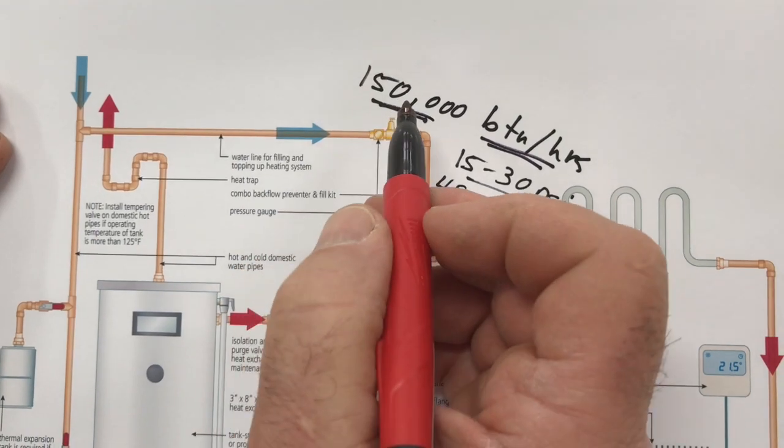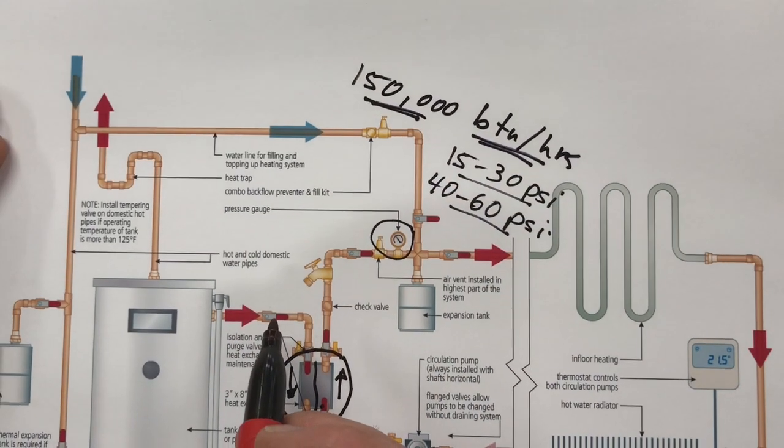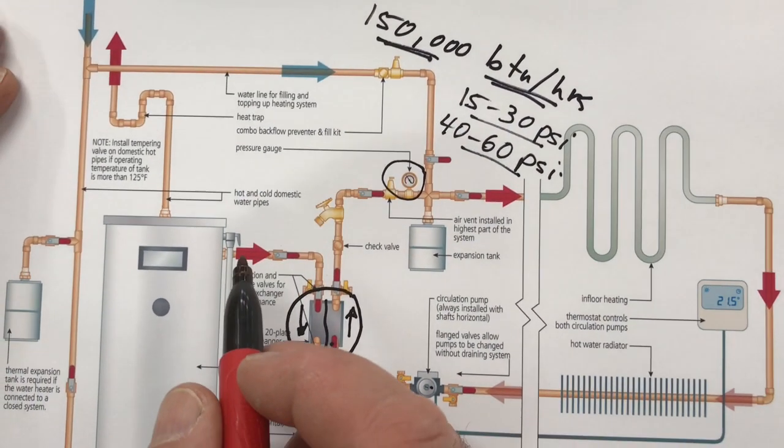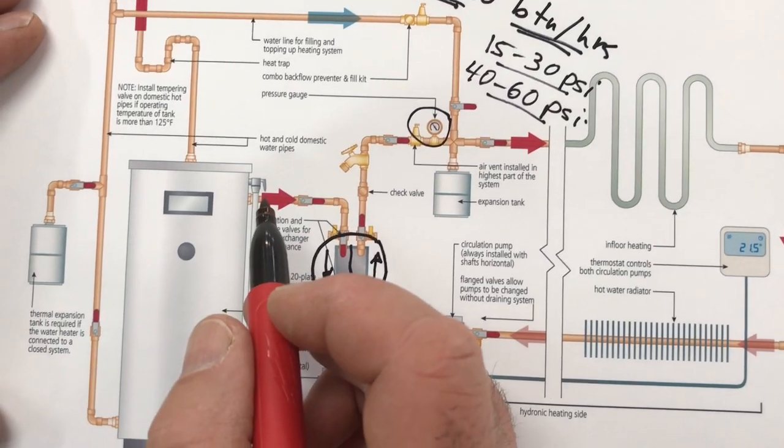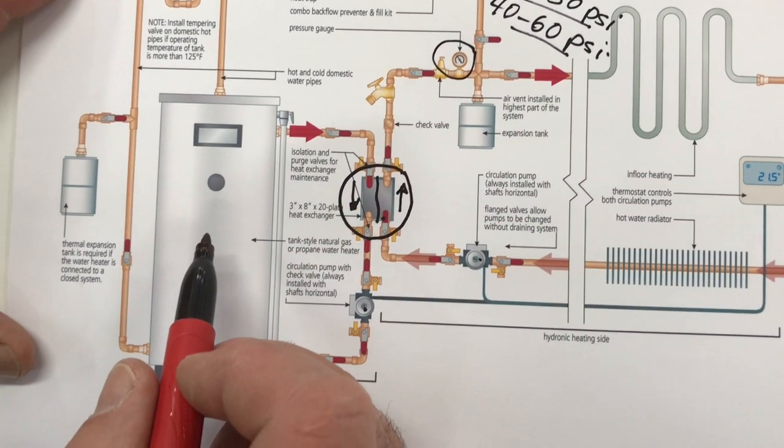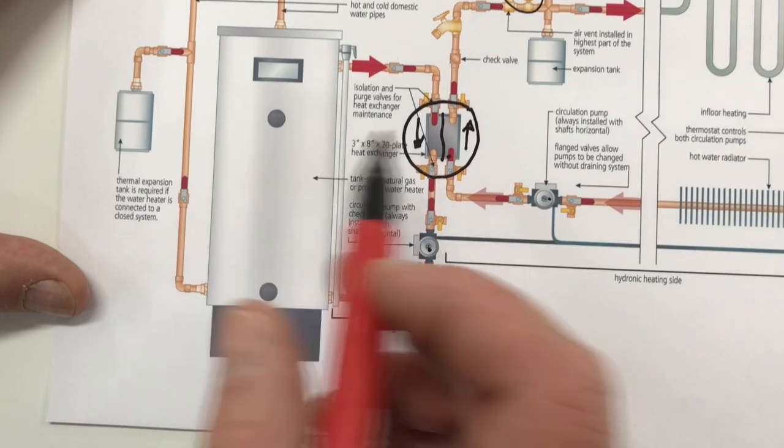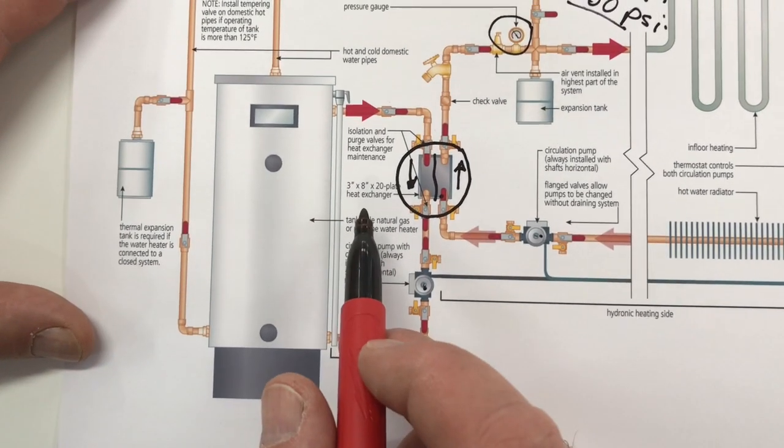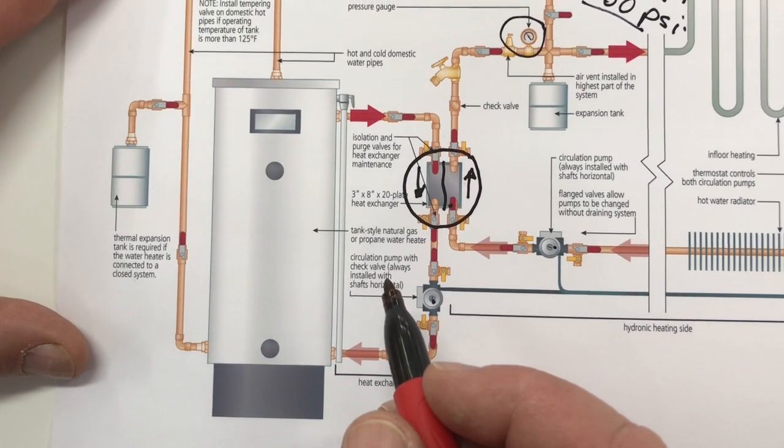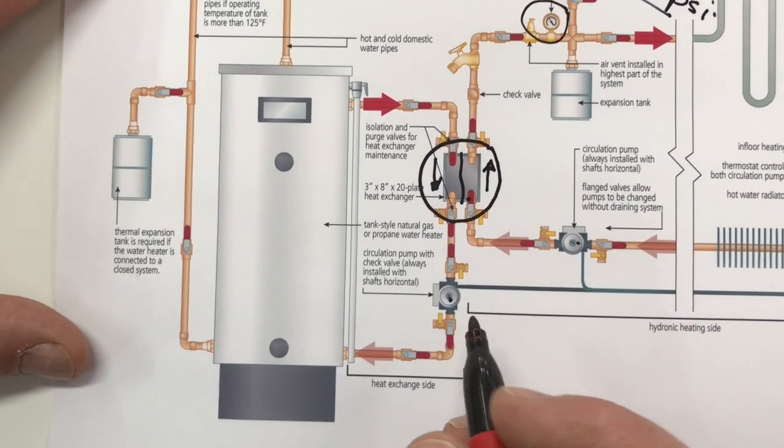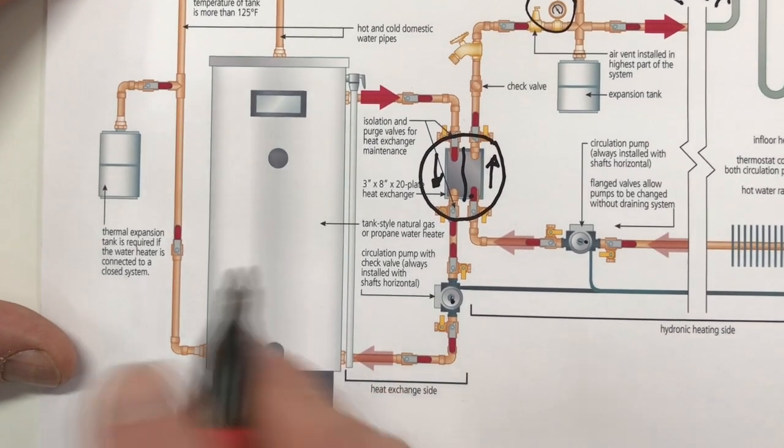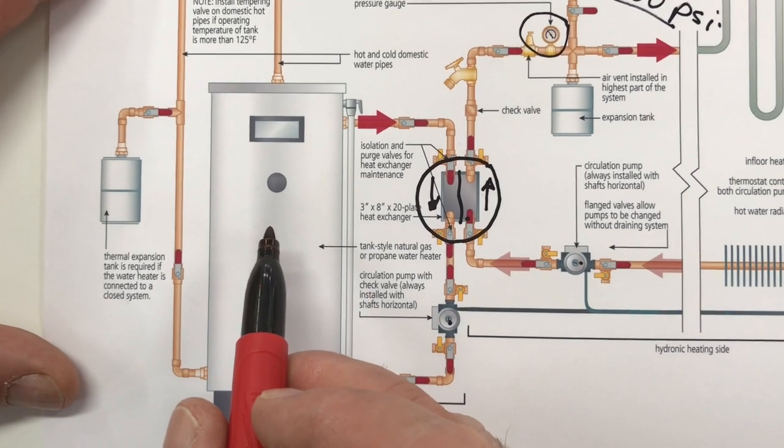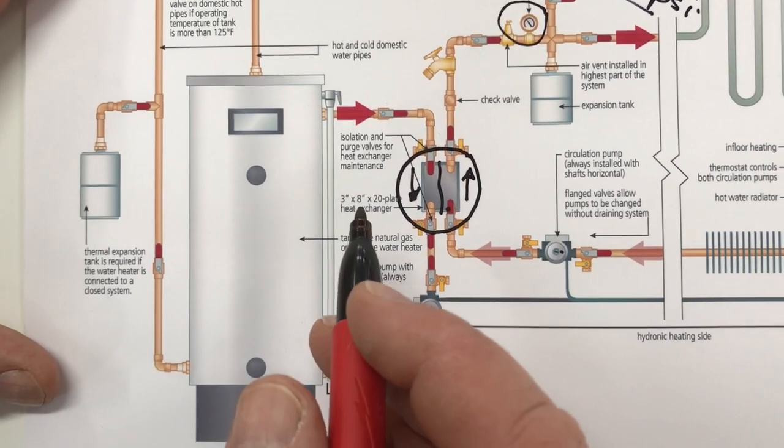But the heater also has to be able to put out heat more consistently. It's going to have a far shorter rest period when it's used as a space heating engine so you need to have a water heater that's up to the job and the manufacturer can tell you that. Some companies will not warrant their tank style heaters for this application and others will.